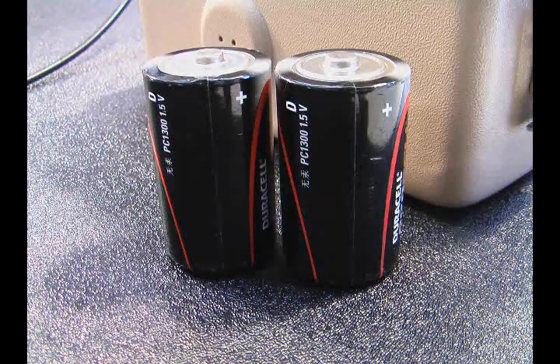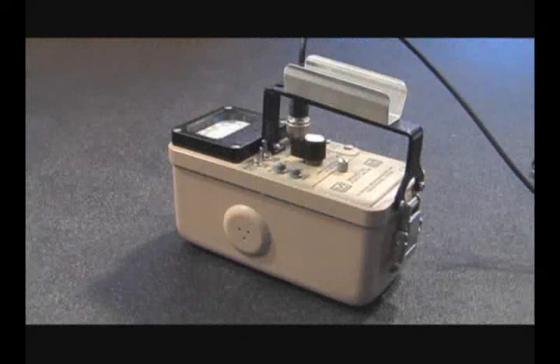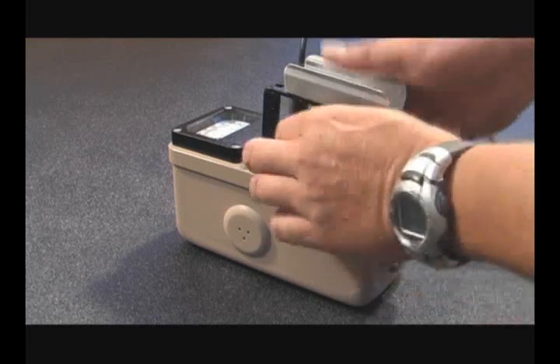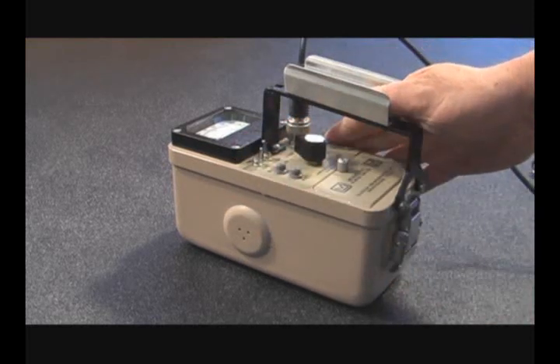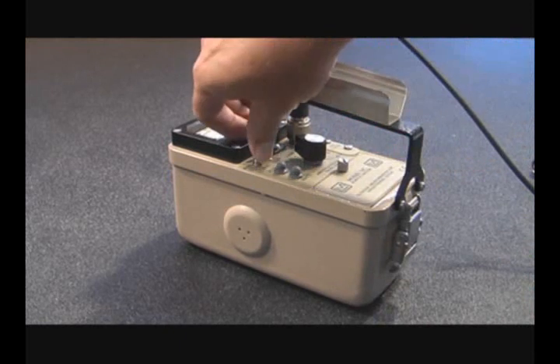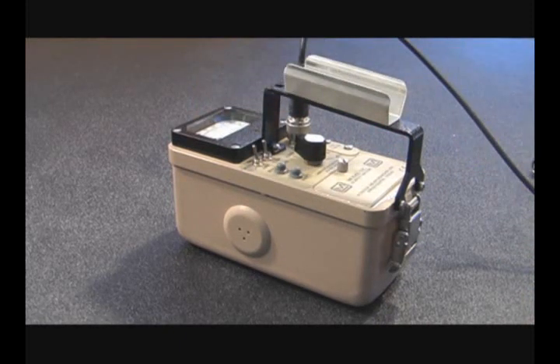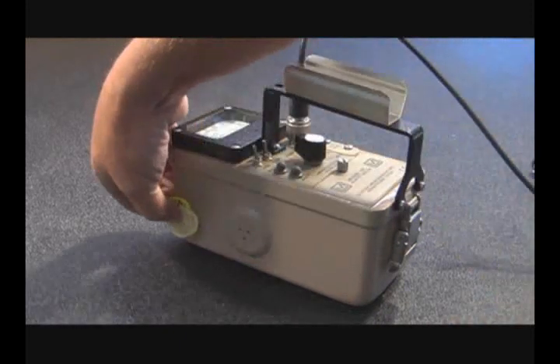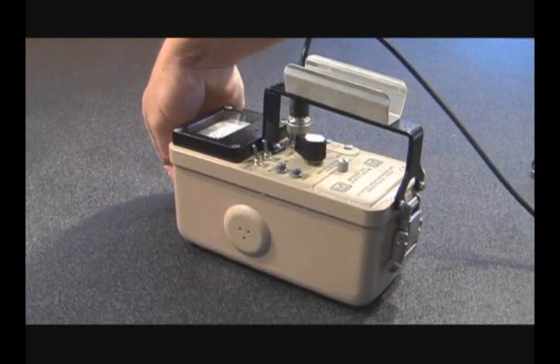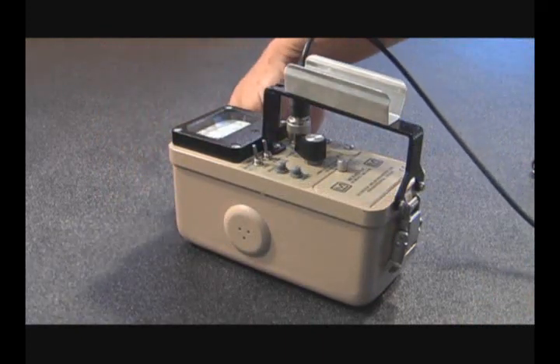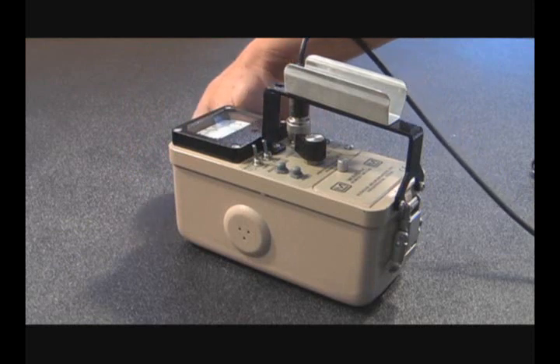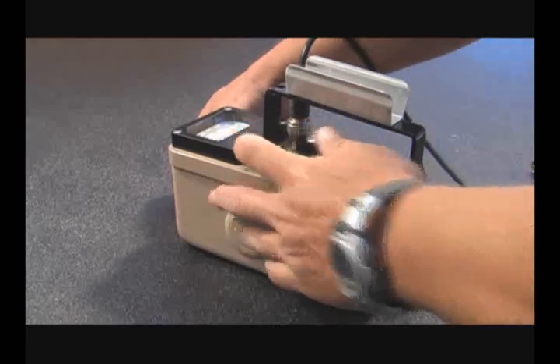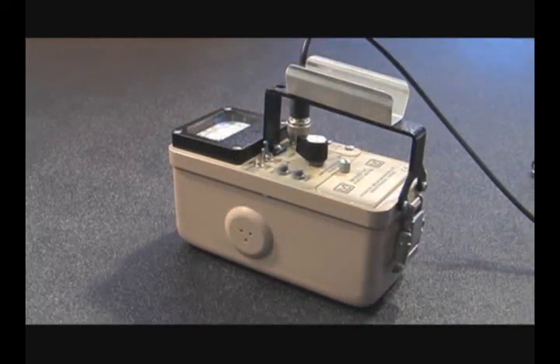After checking the batteries, an operational check should be performed to ensure proper operation between calibrations and periods of non-use. Turn the range switch to the times 1000 position. Turn the audio switch to the on position. Expose the internal detector to a check source. The Unimorph speaker should emit clicks relative to the rate of counts detected. Turning the audio switch off will silence the audible clicks. It is recommended that the audio be kept in the off position when not needed to preserve battery life.